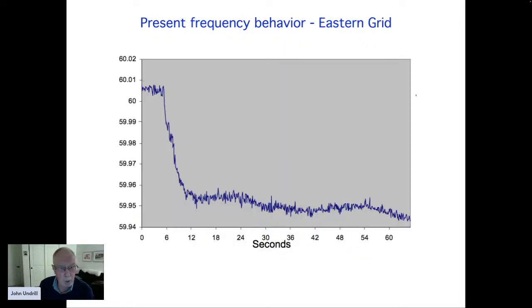Here's the behavior of the Eastern USA grid in a bad event where a lot of generation was lost very suddenly, and the frequency dipped a little bit further than perhaps the simulation would have anticipated, and then didn't come back. Now, in 6 seconds from here to here, people in control rooms can't do anything. They see the screen change, they see the warning message on their screen, but you can't do anything in 6 seconds, and you need to think before you do anything anyway.